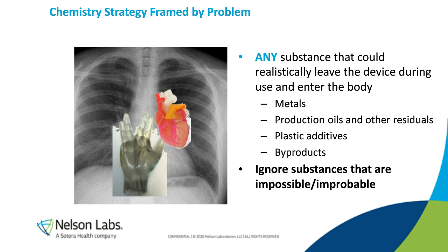It's throughout the new ISO 10993-18. It's mentioned many times, and I think that's really important to remember as a seismic shift in the attitude of how we are supposed to do this chemistry from today to 5 years ago: we've really changed to a focus on these open screens and doing these open screening type studies in as high a quality a manner as possible.